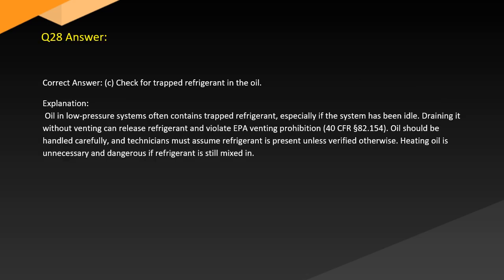Answer. Correct answer: C. Check for trapped refrigerant in the oil. Explanation. Oil in low-pressure systems often contains trapped refrigerant, especially if the system has been idle. Draining it without venting can release refrigerant and violate the EPA venting prohibition, 40 CFR 82.154. Oil should be handled carefully, and technicians must assume refrigerant is present unless verified otherwise. Heating oil is unnecessary and dangerous if refrigerant is still mixed in.